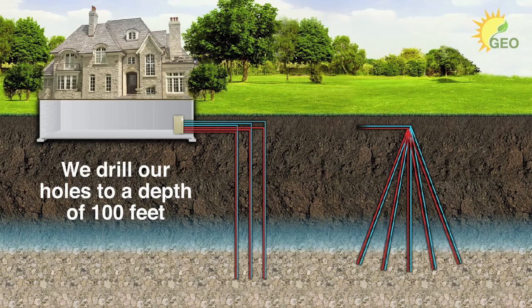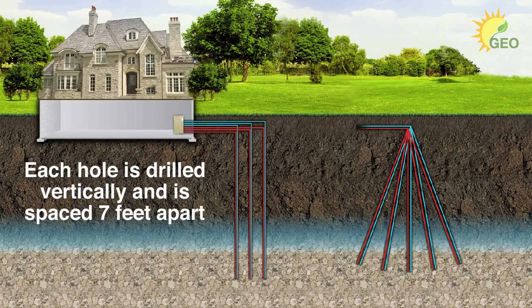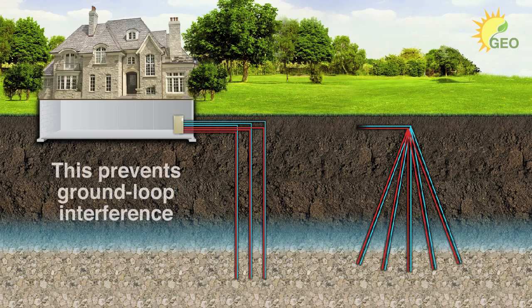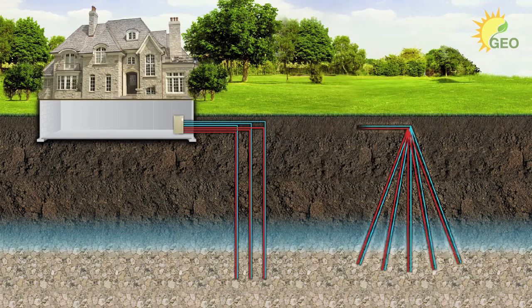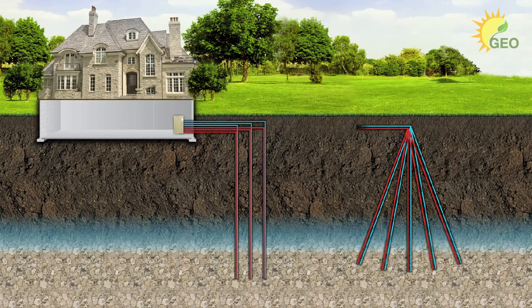Our equipment and installation are what separates us from everyone else. We drill our boreholes to a depth of 100 feet. When drilling to 100 feet, we are very likely to encounter moist soil and or rock conditions, which are preferred for conductivity. Each borehole is drilled vertically and is spaced 7 feet apart. This prevents the phenomenon of ground loop interference.